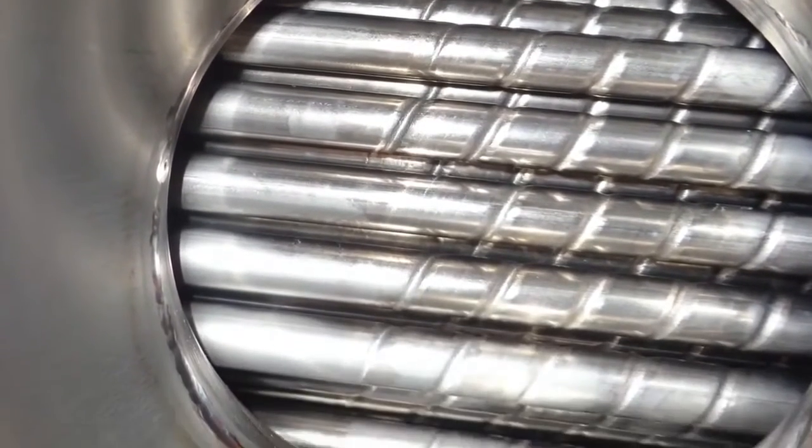They are exchangers that are used, for example, in the cogeneration sector as recoverers on the exhaust fumes of engines. I pass fumes through pipes. They are also used for biogas dehumidification: I pass biogas through pipes, and outside there is glycolated water, which is therefore clean. In the pipes, if my biogas releases impurities, I can clean them. Also used for hot water production with steam: in the mantle, steam passes. Water flows, gets heated in the pipes, and comes out heated.